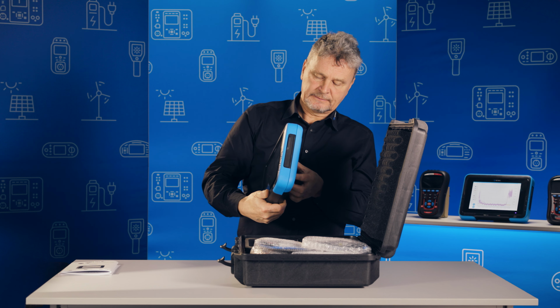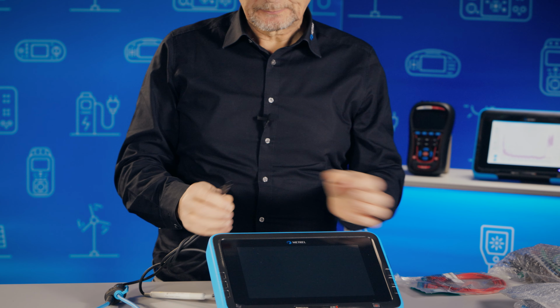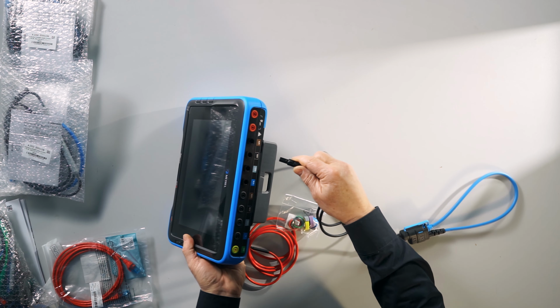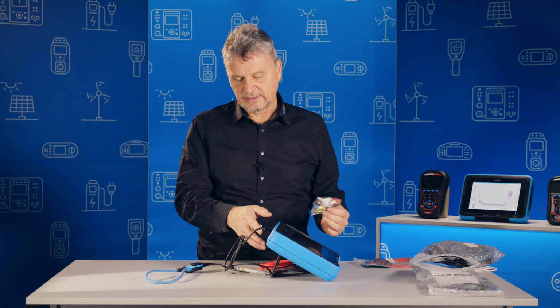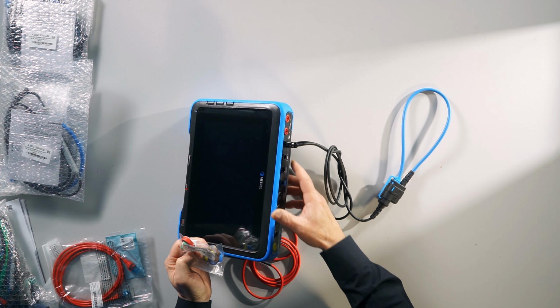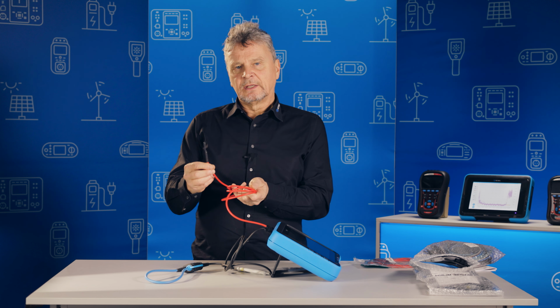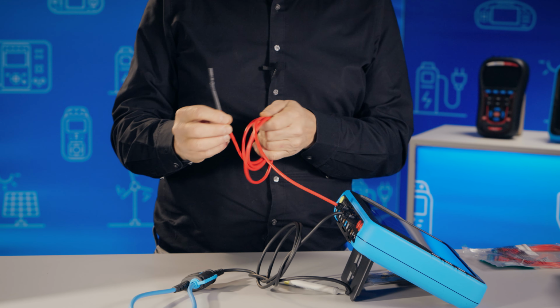Let's check the current clamps first. The flex clamps have a very easy locking and unlocking mechanism, and our flex clamps have 3 different ranges. For example, this clamp A1502 has 30, 300 and 3000 amps. And MI2992 can select the range automatically by itself according to the current consumption. There is a special current sensor, the current terminal, and you have 4 current terminals which are color coded. Additionally, you have marking rings which can be attached directly to the current clamps, so you can easily differentiate which current clamp is related to channel 1, 2 or 3. Into the current input you can also attach a temperature sensor in case you need, for example, to measure the temperature of a transformer during the recording.